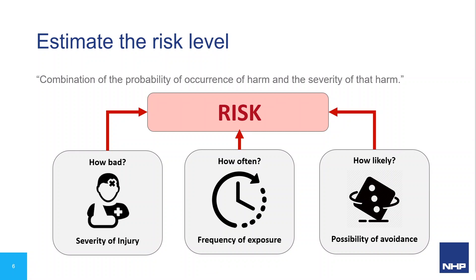Once we've identified hazards likely to cause a problem, we need to determine whether the hazard carries an unacceptable level of risk. We consider: how bad is the injury — a bruised hand or a lost hand? How often is someone exposed — once a year for 15 minutes, or continuously? And if someone finds themselves in a hazardous situation, how likely are they to enact self-preservation? Is it a slow-moving steamroller, or a rapidly moving robot arm you can't duck in time to avoid?